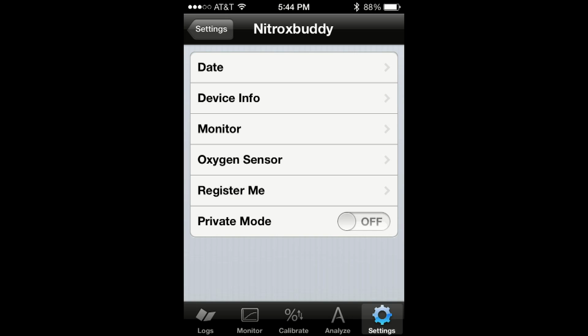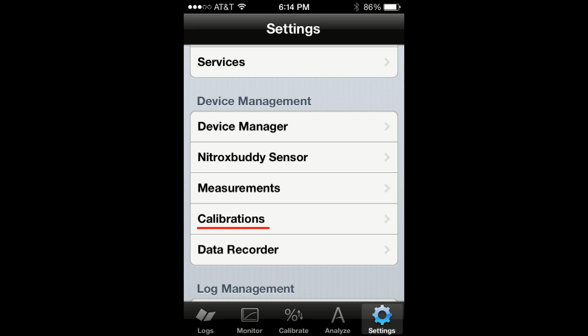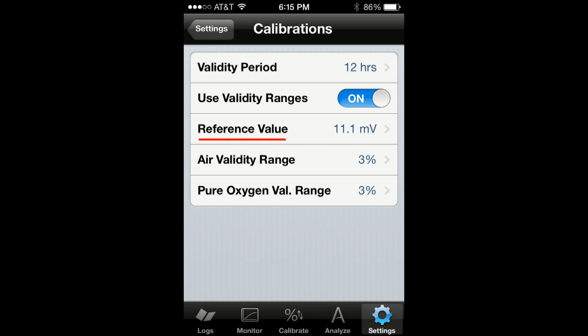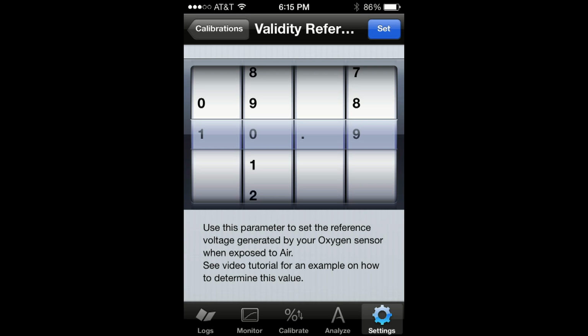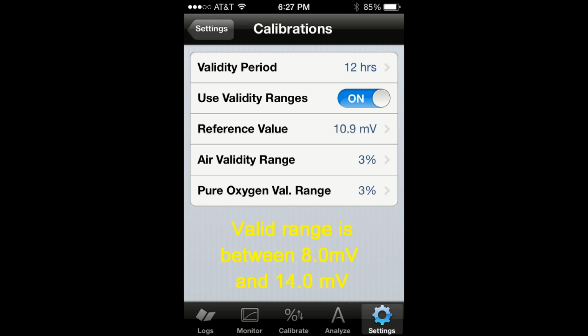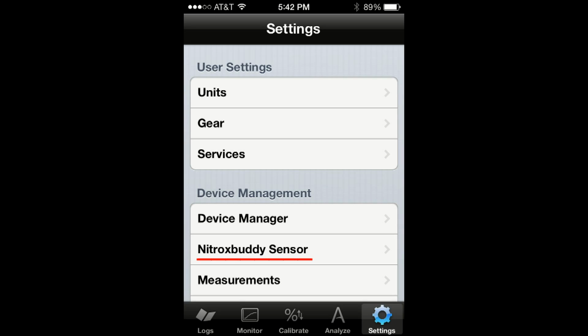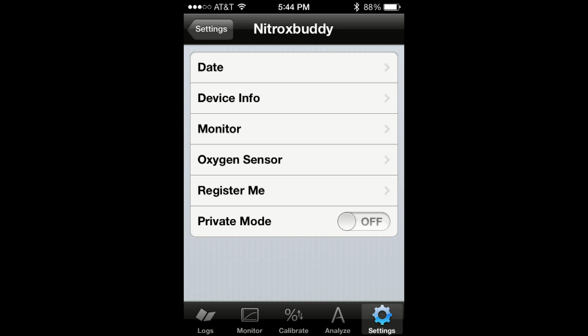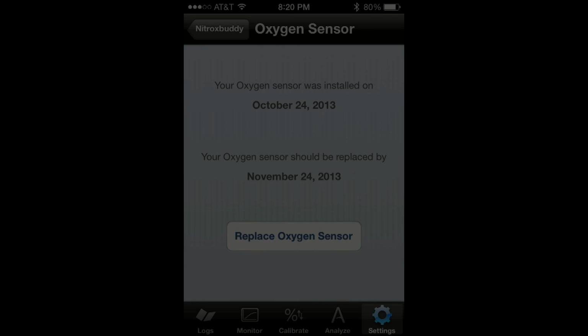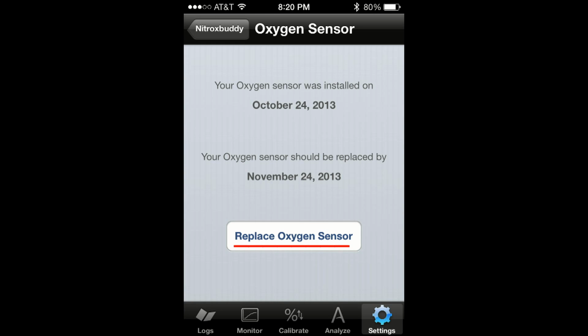Go back to Settings and tap on Calibrations. Then tap on Reference Value and enter the output value you just wrote down. We're almost done. One more step. We need to set the oxygen sensor lifetime. Go to the Nitroxbuddy sensor settings. Tap on Oxygen Sensor, then tap on Replace Oxygen Sensor.